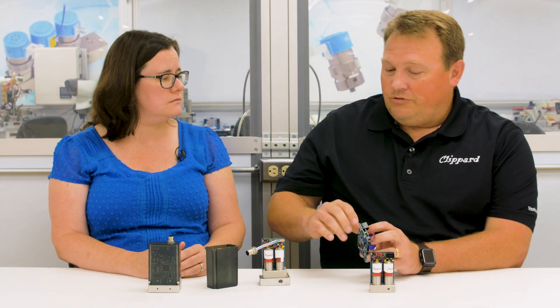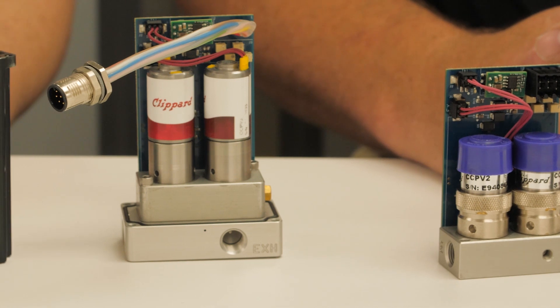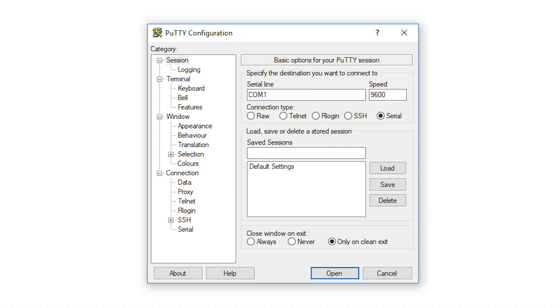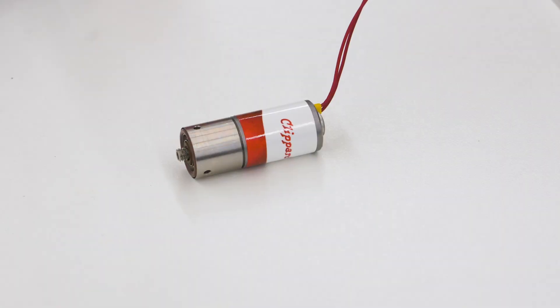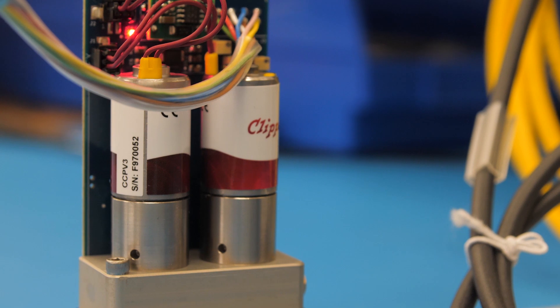The customer is actually able to — and we want them to — through a 3.3 volt serial communication, log into the unit and adjust the P&I settings directly at the machine, based specifically on what they need the unit to do. These settings will be able to adjust the accuracy, hysteresis, and stability of the unit and put that decision in the customer's hands.